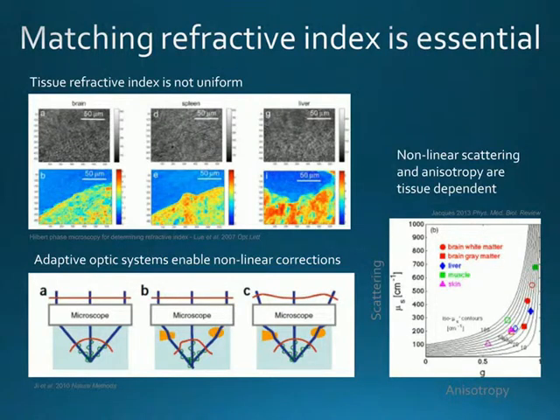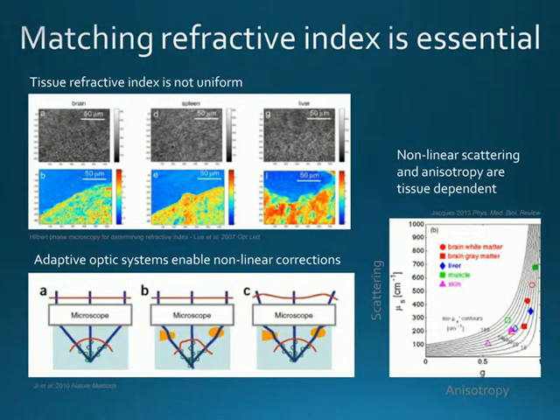There's also a lot of nonlinear scattering through the tissue and anisotropy that will be tissue-dependent, so you want the technique to be as universal as possible. Some researchers at Janelia Farm have helped solve this by looking at adaptive optic systems, which work by changing the wavefront of light going through the microscope. In a normal condition you can focus to a point easily, but with elements in the tissue deflecting light due to differences in refractive index, the wavefront doesn't focus at a sharp point. However, adaptive optic systems are rather new, not in many multi-user facilities, and can be rather slow.